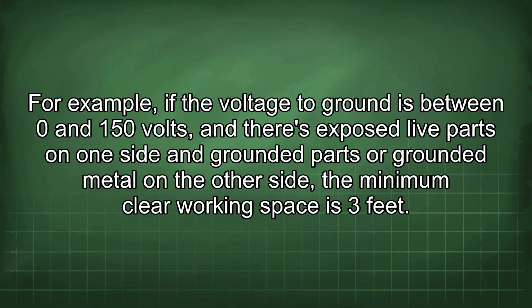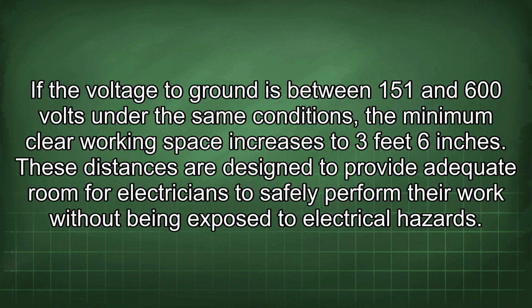For example, if the voltage to ground is between 0 and 150 volts, and there are exposed live parts on one side and grounded parts or grounded metal on the other side, the minimum clear working space is 3 feet. If the voltage to ground is between 151 and 600 volts under the same conditions, the minimum clear working space increases to 3 feet 6 inches.